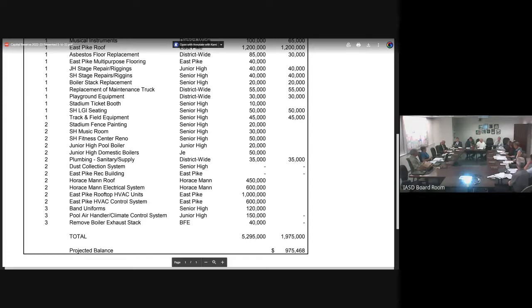What about the pool air handler? I thought we discussed that a year or two ago and it needed replacing. That's the same age as the boiler, which is why I asked to have the boiler added, because of their renovation. Should the air handler move up? It's 17 years old, the same age as the roof, and it has exceeded its life. Should the air handler be moved up to number 2? Yes, they should be together with the boiler, one system.